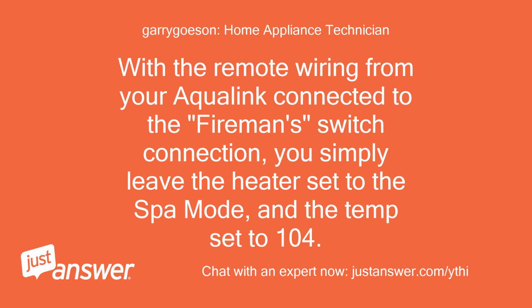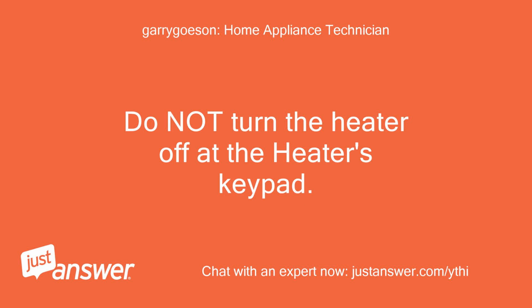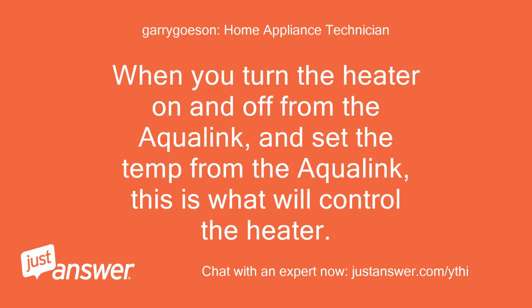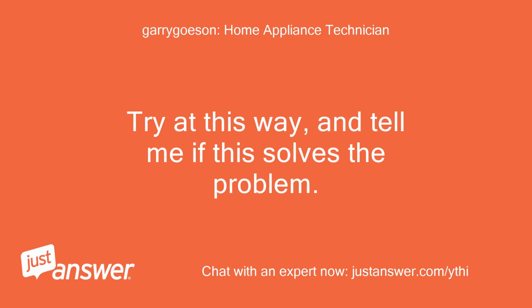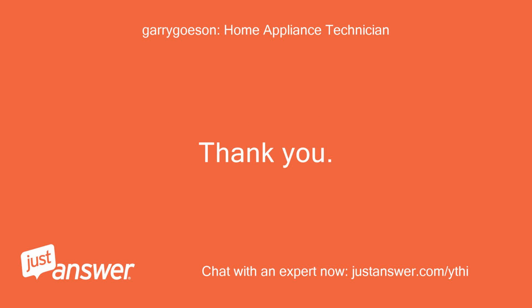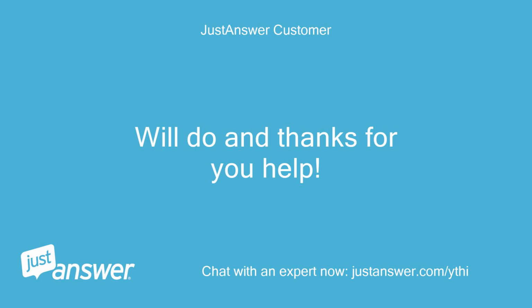With the remote wiring from your Aqualink connected to the fireman switch connection, you simply leave the heater set to the spa mode, and the temp set to 104. Do not turn the heater off at the heater's keypad. When you turn the heater on and off from the Aqualink, and set the temp from the Aqualink, this is what will control the heater. Try it this way, and tell me if this solves the problem. Thank you. Will do, and thanks for your help.